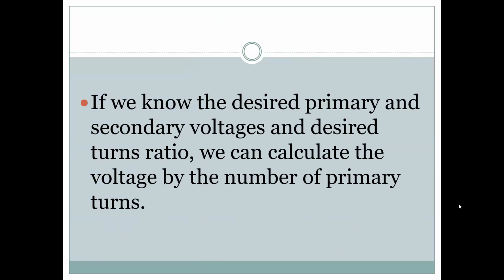Next. If you know the desired primary and secondary voltage and the turns ratio, we can calculate the voltage per turn and the number of primary turns. So primary turns and all we can find out, and the designer starts working on that. Very simple design of that. Now nobody designs manually nowadays, it is only feedback, and the computer gives you the most optimum design available.